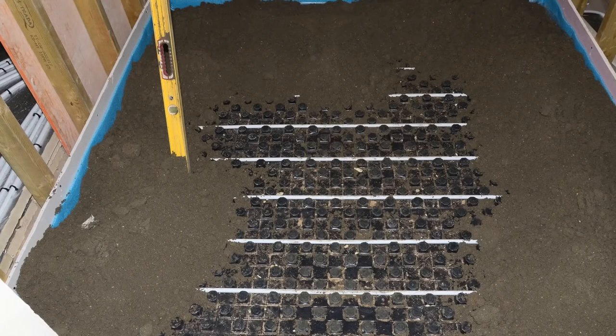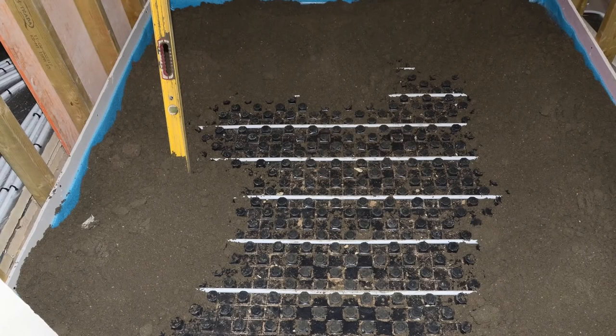When laying the screed, care should be taken to ensure that the screed is compacted around the pipe properly. Most screeded floors require 28 days after laying before preheating can begin.